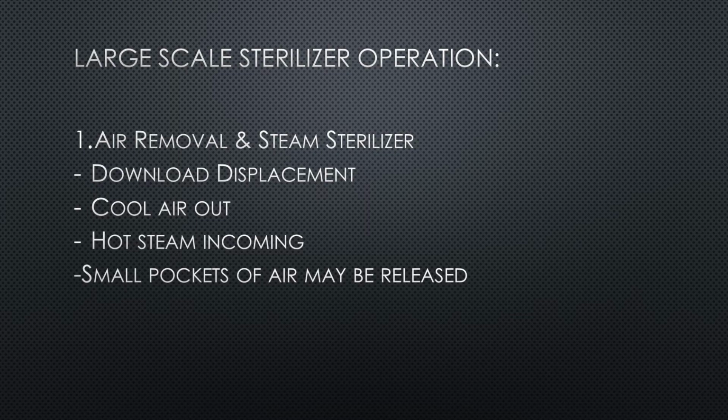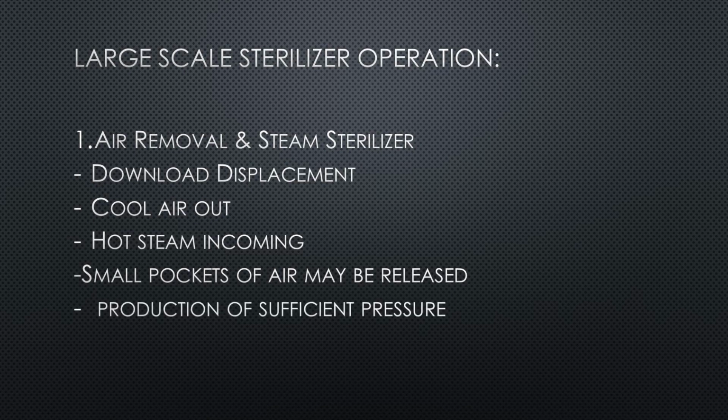Suppose we are having the intravenous fluids packed into flexible plastic containers. During their sterilization, considerable internal pressure in the airspace above the fluid can be developed. It is necessary to maintain the proportion of air within the chamber to produce sufficient overpressure to prevent these containers from bursting.